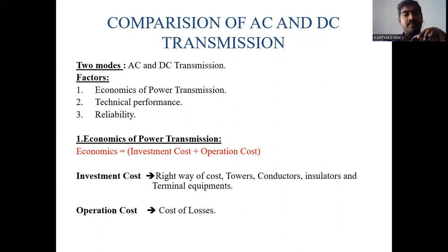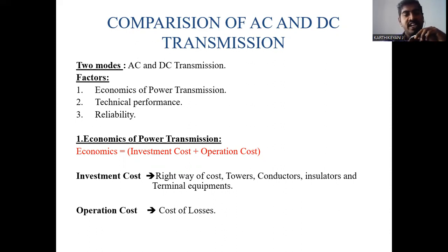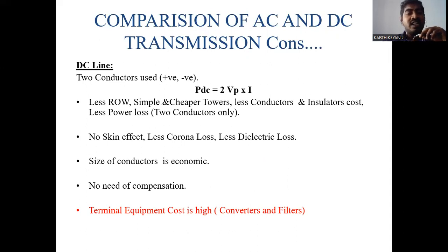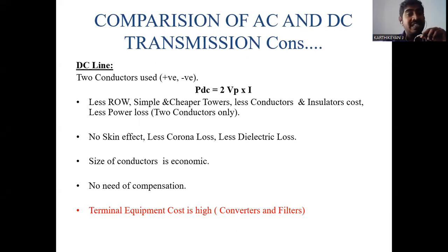There are two modes of transmission — AC and DC. The factors to be considered while transmitting power are: economics of power transmission, technical performance, and reliability. Economic factors include investment cost, operating cost, and conductor cost. In AC transmission, losses include the skin effect, Ferranti effect, corona loss, and magnetic interference. In DC transmission, there is no skin effect, less corona loss, less dielectric losses, and the conductor size is also more economical.